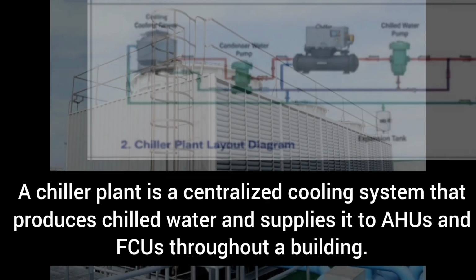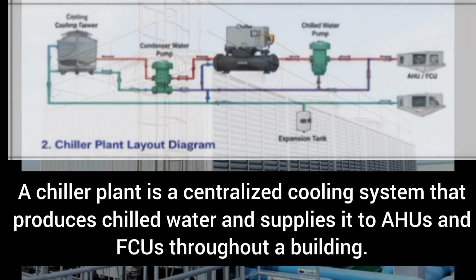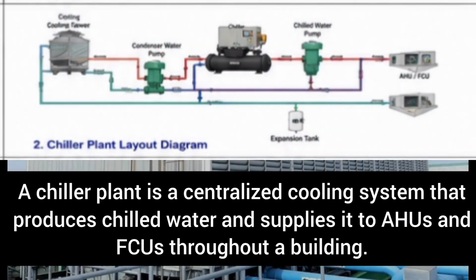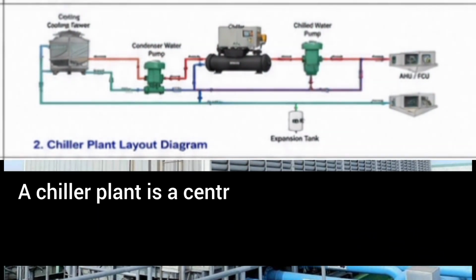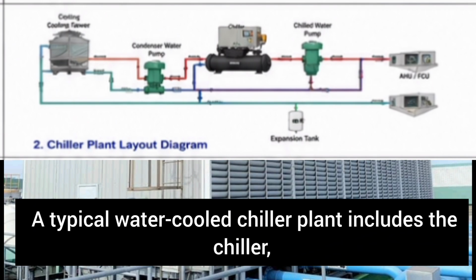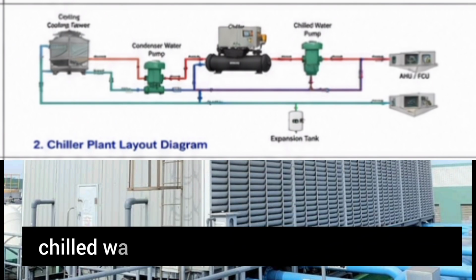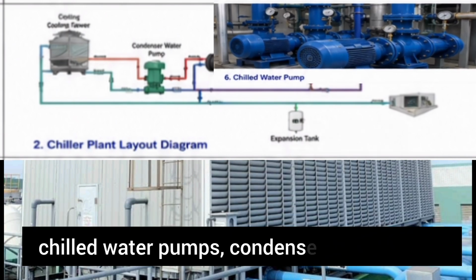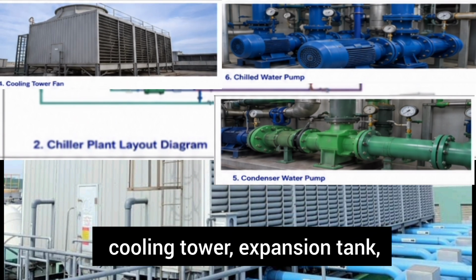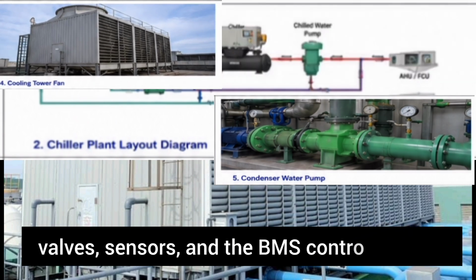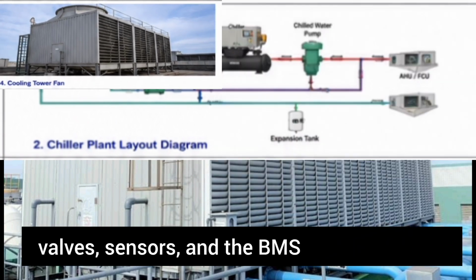Let's get started. What is a chiller plant? A chiller plant is a centralized cooling system that produces chilled water and supplies it to AHUs and FCUs throughout a building. A typical water-cooled chiller plant includes the chiller, chilled water pumps, condenser water pumps, cooling tower, expansion tank, valves, sensors, and the BMS control system.